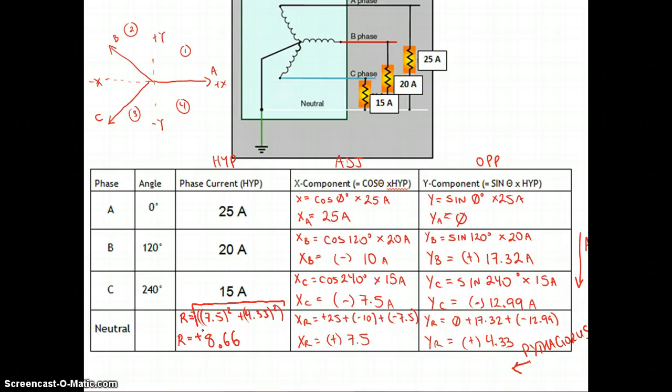Okay, so now we've got our neutral current. If we have 25 amps on A, 20 amps on B, 15 amps on C, we end up with a neutral current of 8.66 amps. Now, if we were to draw this triangle now, we have all the components there for that neutral current. This 7.5 ends up being the adjacent, the 4.33 ends up being the opposite, and the 8.66 for our neutral current ends up being the hypotenuse.